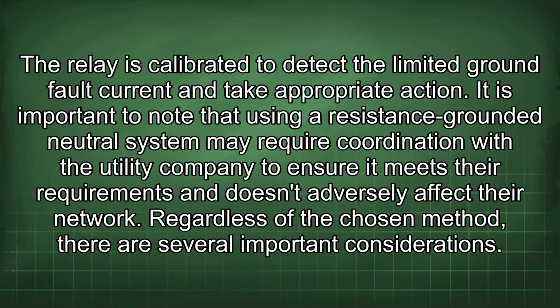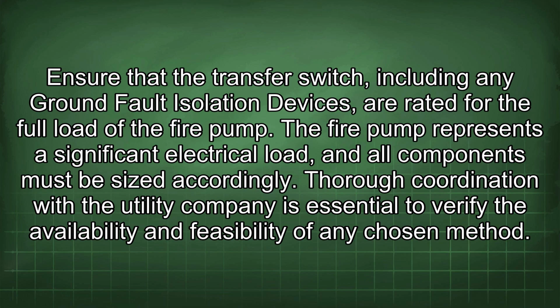It is important to note that using a resistance-grounded neutral system may require coordination with the utility company to ensure it meets their requirements and doesn't adversely affect their network. Regardless of the chosen method, there are several important considerations. Ensure that the transfer switch, including any ground fault isolation devices, are rated for the full load of the fire pump. The fire pump represents a significant electrical load, and all components must be sized accordingly.